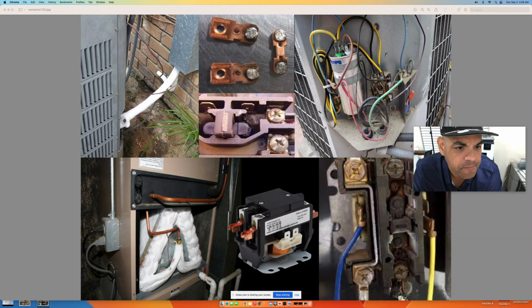Okay, the main difference between the capacitors, and why these capacitors go out so often, is remember capacitors actually have an oil inside of that capacitor. So you've got oil in that capacitor that will cause an expansion with the heat. Contactors don't have oil in them. They're just plastic and metal parts that don't really have expansion. They do have normal wear and tear though when they go up and down. So that's probably the only wear and tear that you're going to have. But I would worry more about your capacitor and replace your capacitor maybe every 3 years, especially if you live in a really hot climate that gets close to 100 degrees.